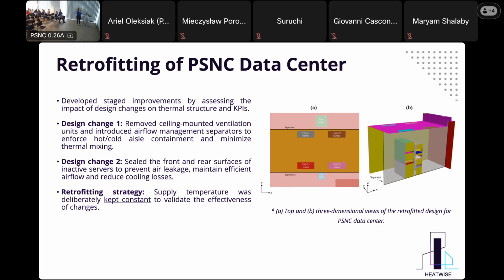So design change 1, removed ceiling mounted ventilation units and introduced airflow management separators to enforce hot and cold aisle containment and minimize thermal mixing. Design change 2, sealed the front and rear surfaces of inactive servers to prevent undesired heat transfer and to prevent air leakage, maintain efficient airflow and reduce cooling losses.